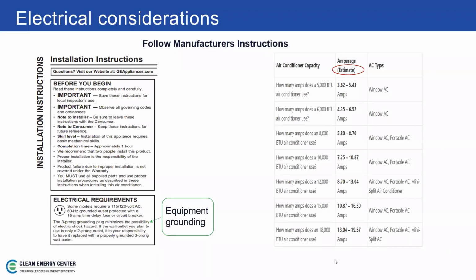This is just an estimate over here, so you can't use this chart to actually make those calls. You have to have that piece of equipment sitting at your feet so you can take a look at it. But as an idea, how many amps does a 5,000 BTU air conditioner use? Somewhere between 3.6 and 5. So you may be okay with your smaller units, but when you get up to 8,000 to 10,000 BTU units, your amperage is getting up to where you really need to think about what circuit you're plugging into, or whether you need an electrician to come in and add a circuit.